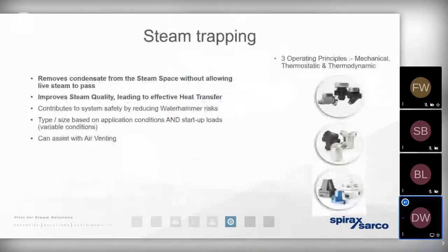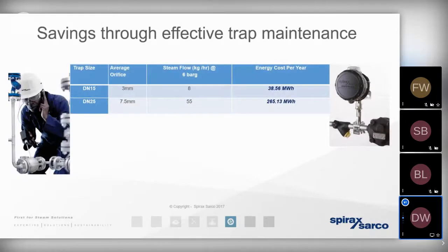So in previous weeks, we've spoken about how it's the steam traps that are perhaps one of the single most important components on the steam distribution loop. If the steam traps aren't sized and selected correctly, then they're highly unlikely to be working efficiently, and sooner or later they are going to fail and result in a significant loss of energy. We remember there's no such thing as a one-size-fits-all universal steam trap, but we also appreciate that if we know a few key variables, if that steam trap were to be left failed in the open position, then we would have a significant mass of steam venting away to atmosphere, a huge inefficiency.